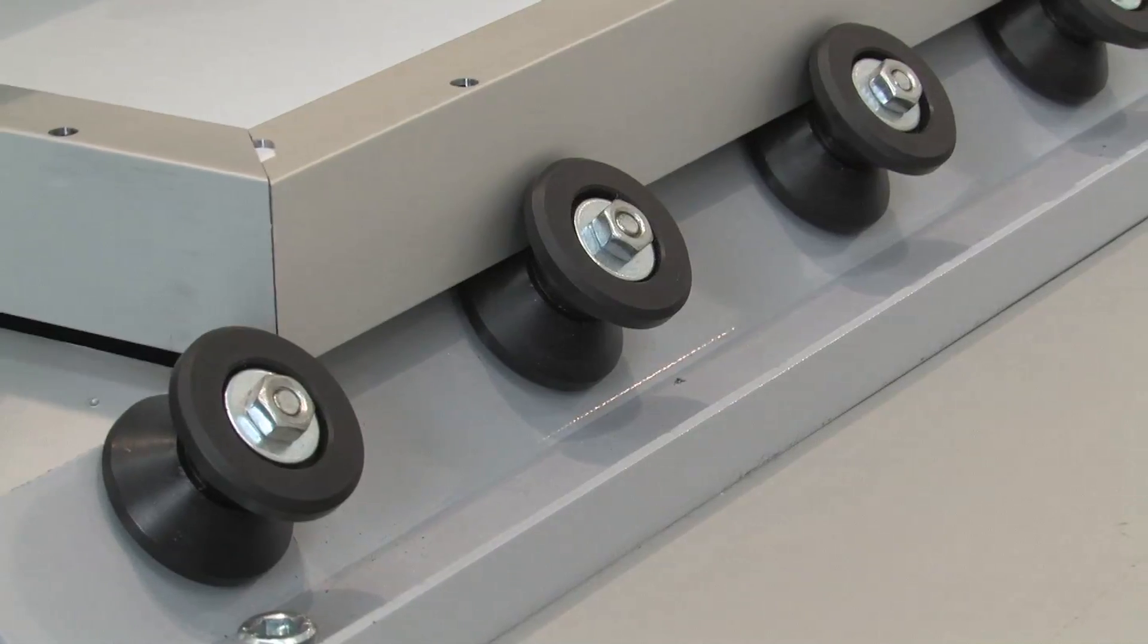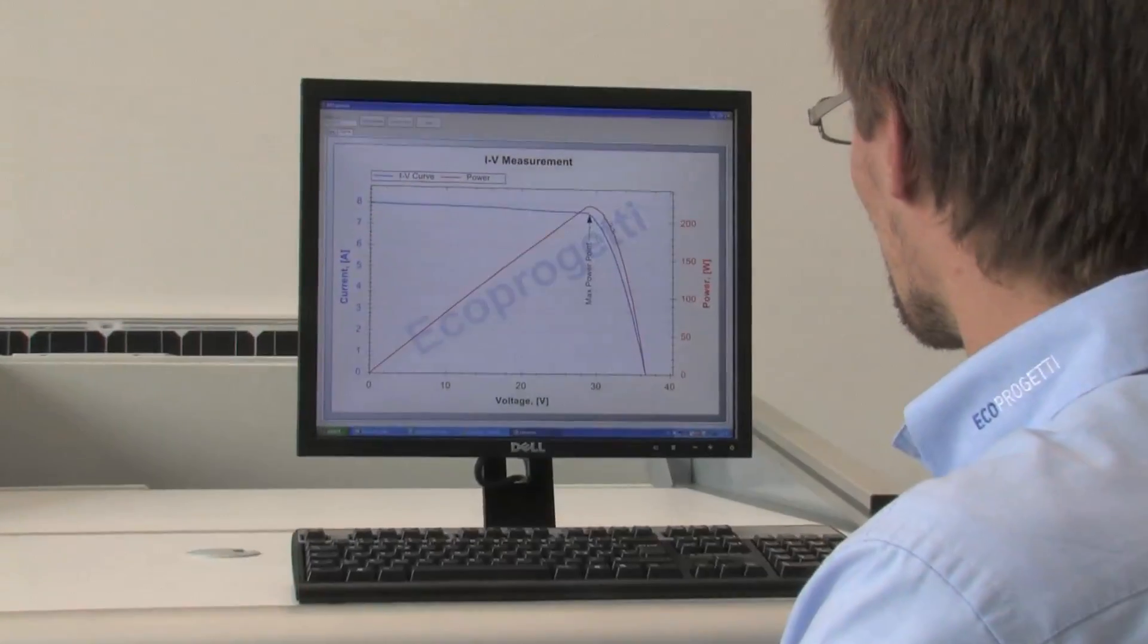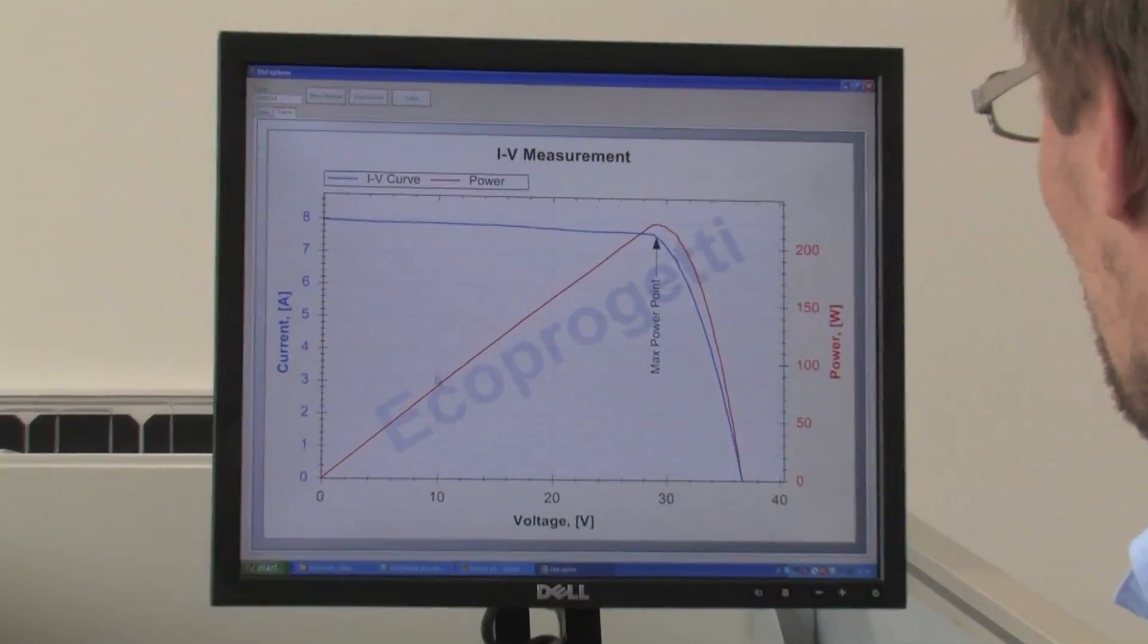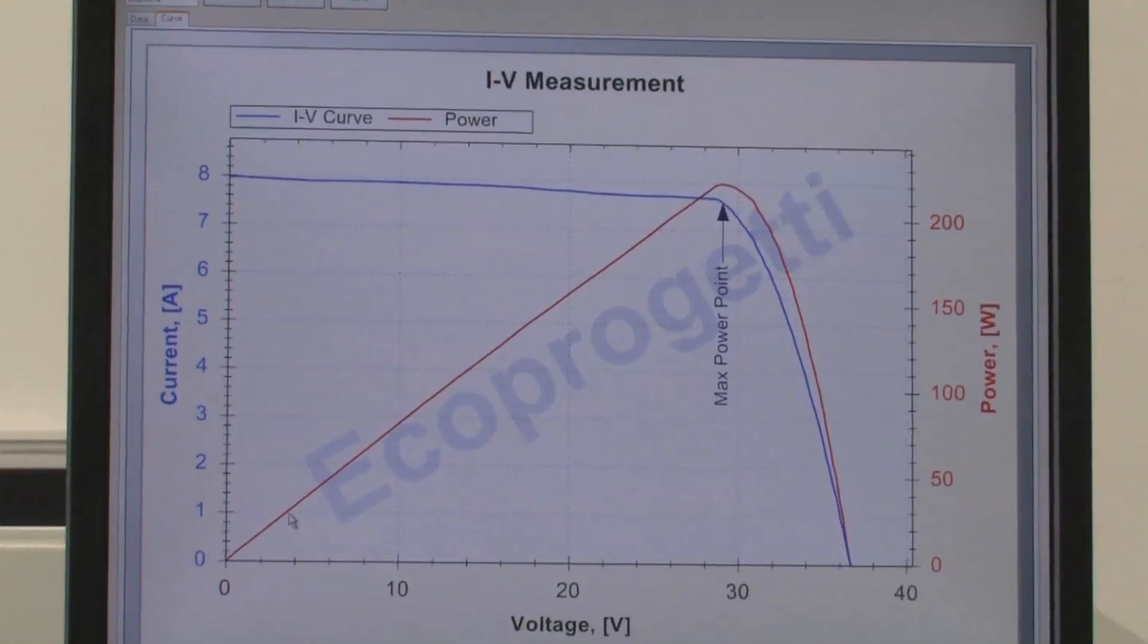This feature, that is possible to obtain with standard flash simulators, is very useful to prevent that the measurement is affected by the capacitive effects of the module. A personalized pulse is very useful both for crystalline products as well as new technologies like thin film and back contact solar cells.